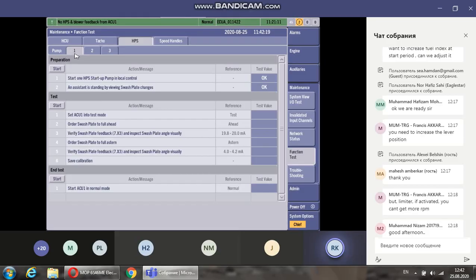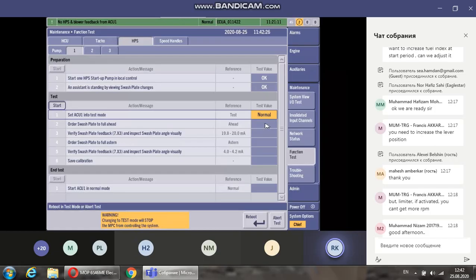Again, you can only do this one pump at a time. So we look at number one, and then we go down here, and we can do exactly the same as we've just done: take it into test mode, go through and order, check the position, and then save the calibration.